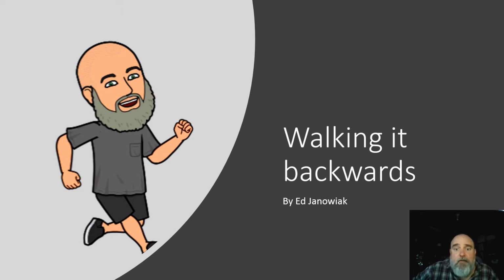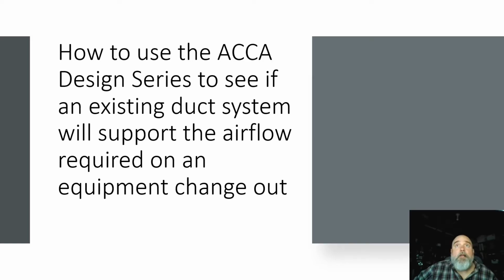Walking it backwards is a reference to using the ACCA Design Series in a way that maybe it was never originally intended to be used. The ACCA Design Series is a series of manuals that show us how to size and select equipment. And what we're going to do is use the books sort of in the same order, but to determine if an existing duct system will support the airflow that we need moving across our new system.